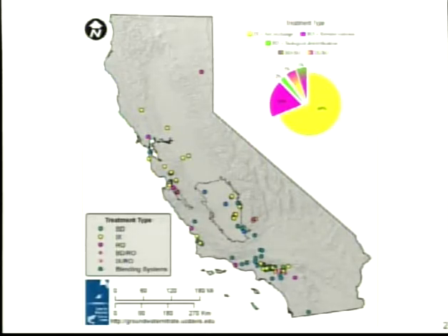I think if you look at the proportion of the systems installed here up in the top, almost 70% of those nitrate systems that are installed to date are ion exchange systems, followed by reverse osmosis, and then you've got the smaller proportions of the biological denitrification systems and then the combinations thereof.